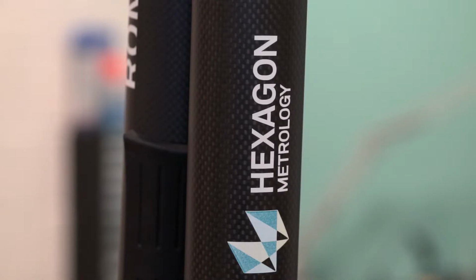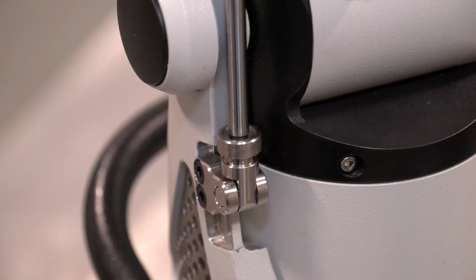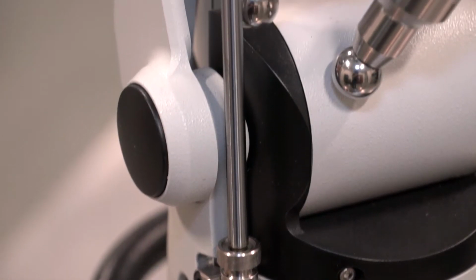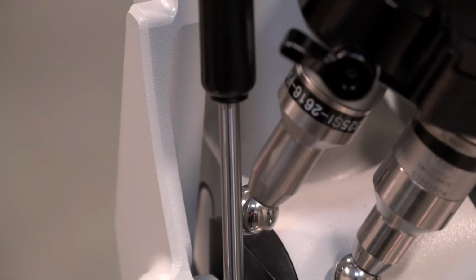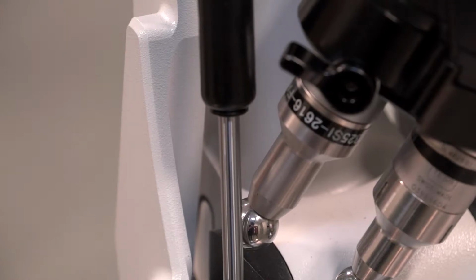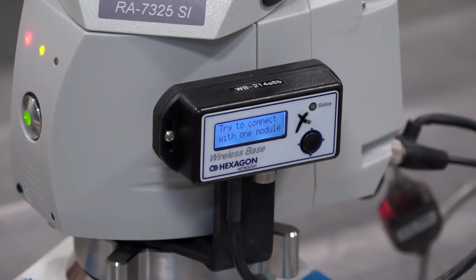John, now we're in your facility in Milton Keynes, but what makes Hexagon Manufacturing Intelligence unique from a service calibration point of view of your Romer arms? Okay, well, typically when an arm comes in for a service and calibration, we check the arm over for damage to any of the components. So on a normal service, we would replace the gas strut if it needed doing. If there's any handles or panels that are cracked, they get replaced. And then we would calibrate the arm after servicing it.